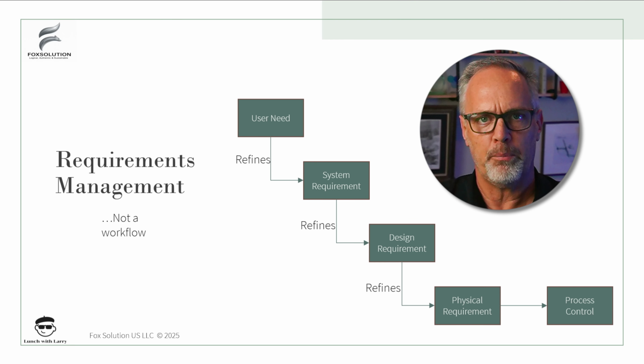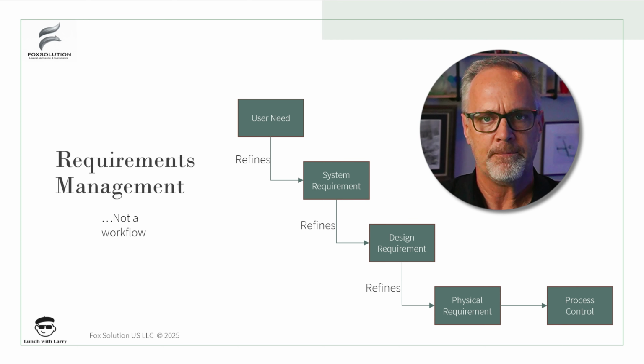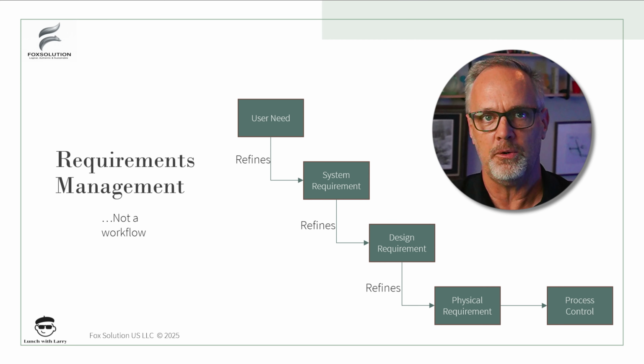So one of the important things to talk about here, a lot of times people look at this as a workflow. It's really not. What this is, is a logical decomposition so that we can explain to people who don't understand how the device works, how the device works. We want to have a very clear construction that I can talk to someone about what we expect to see out of the device and the evidence that we have that it complies. It doesn't mean that I have to do user needs before system requirements or system requirements before physical requirements.